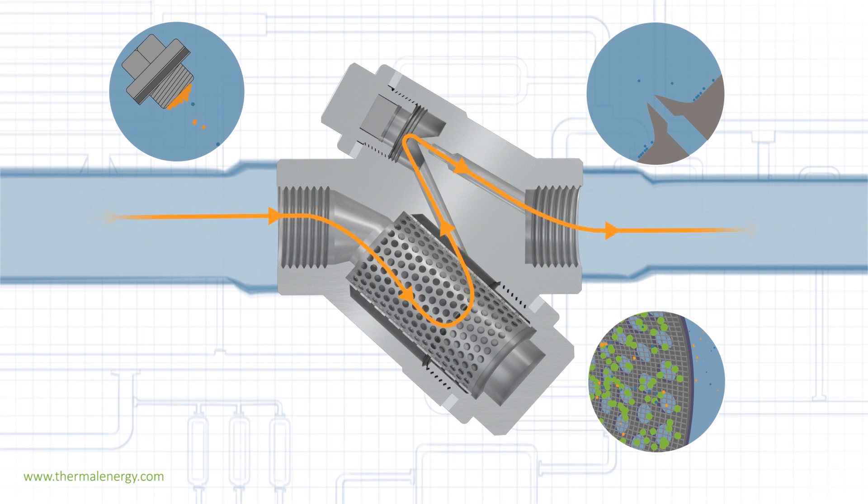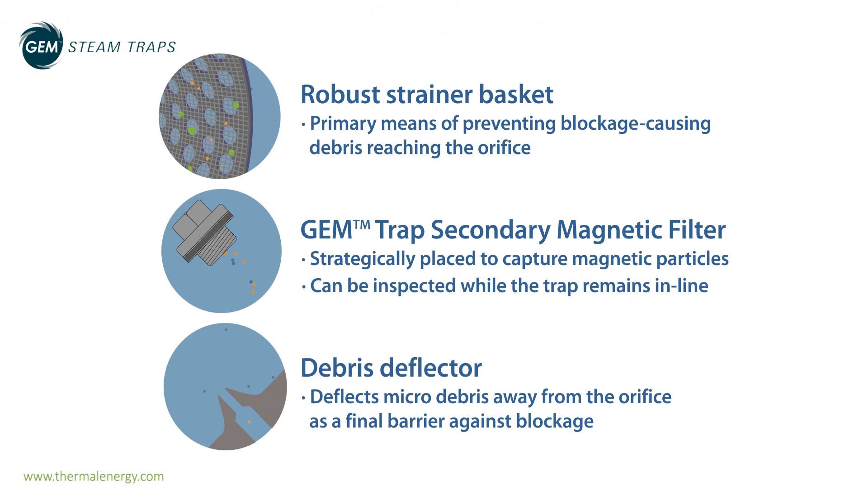Why is this important? For larger processes, due to the orifice size required to accommodate flow rates, blockage is not a significant concern. However, for line drainage, trace heating, and other small-duty applications, a small orifice is required to operate efficiently. Here, protecting the orifice from blockage and ease of maintenance are important factors.